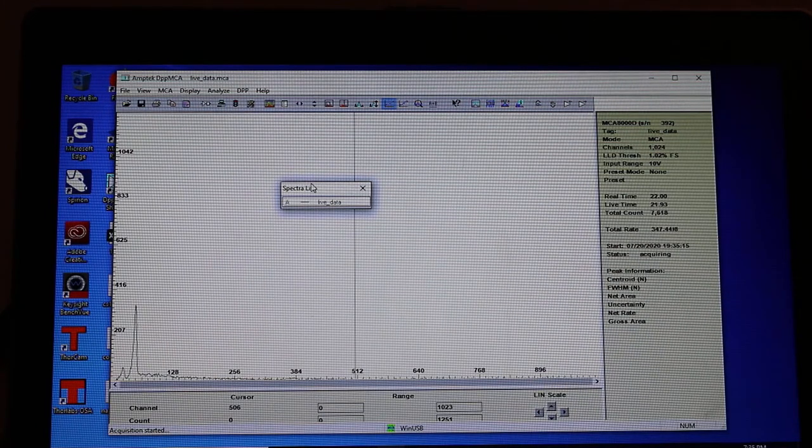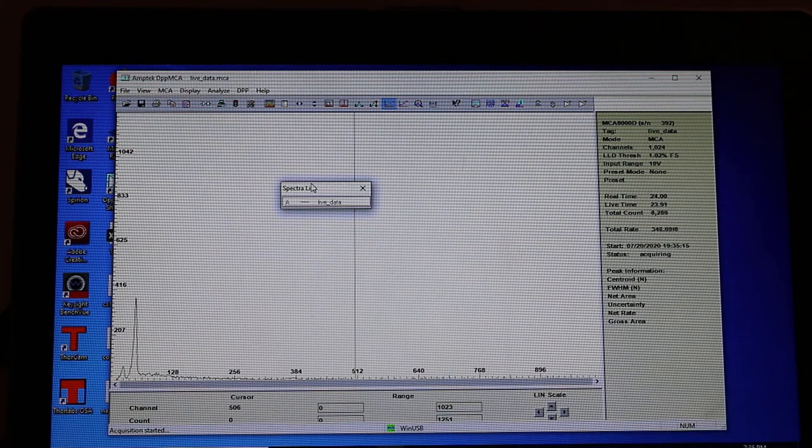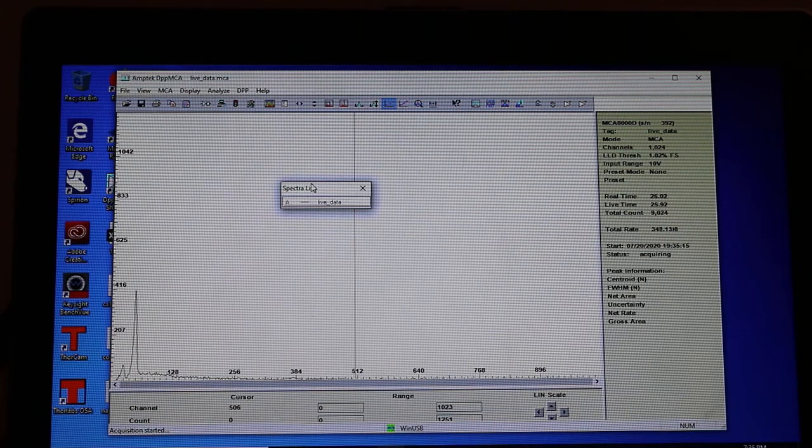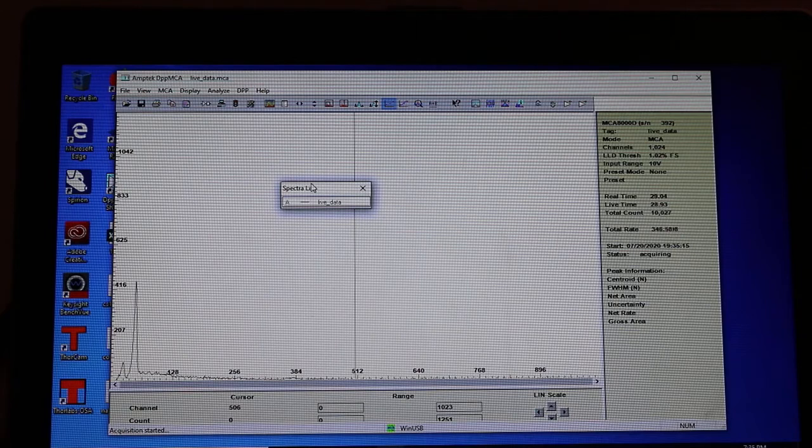Look at the americium 241, very low energy gamma ray emitter, something like 60 keV or so way down there. So it gives you a nice calibration point at those lower channel numbers, doesn't it?